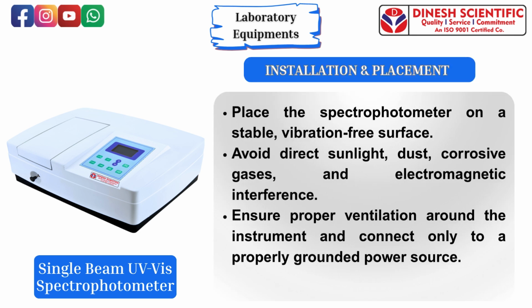Installation or placement. Place the spectrophotometer on a stable, vibration-free surface. Avoid direct sunlight, dust, corrosive gases, and electromagnetic interference. Ensure proper ventilation around the instrument and connect only to a properly grounded power source.